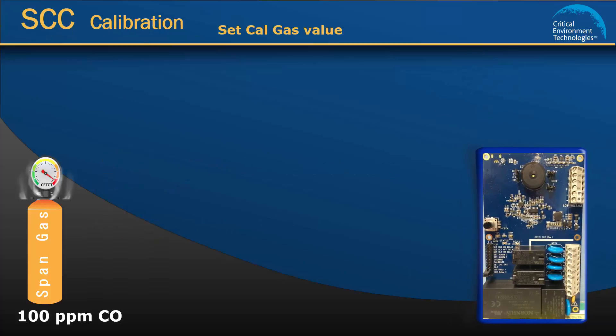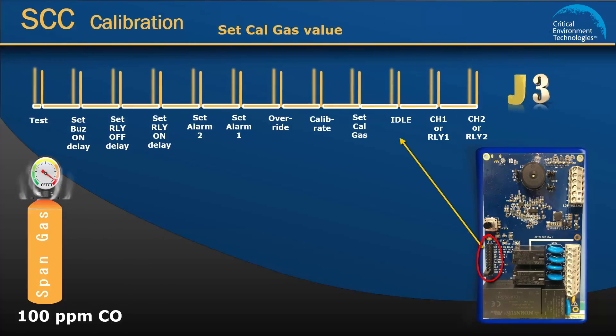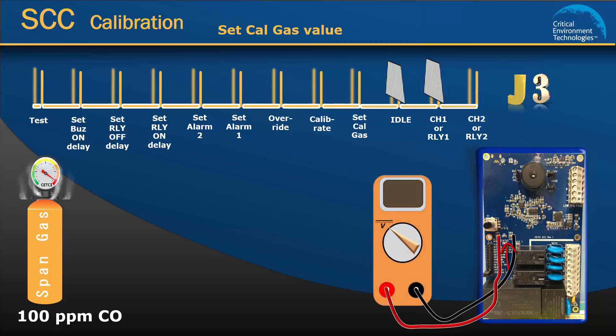Open the SCC and find the jumper bank on the left side of the board. There should be one jumper on idle and one jumper on channel 1. These are the default jumper positions. Find the test points TP1 and TP2 on the board. Attach your voltmeter and keep it attached until the entire calibration procedure is complete.